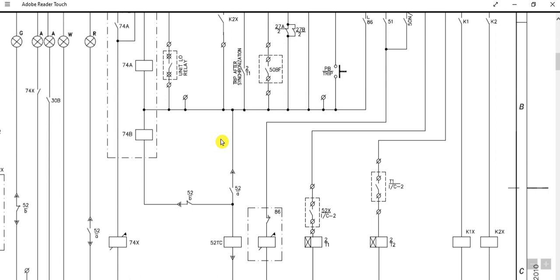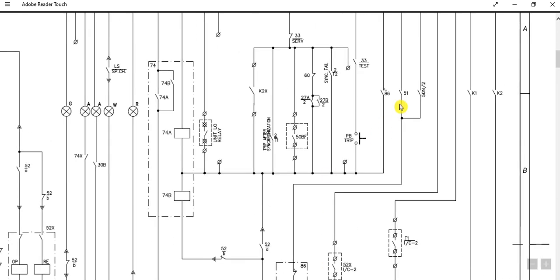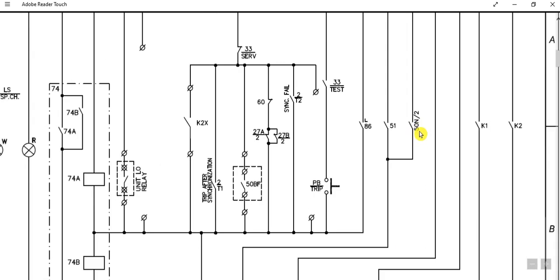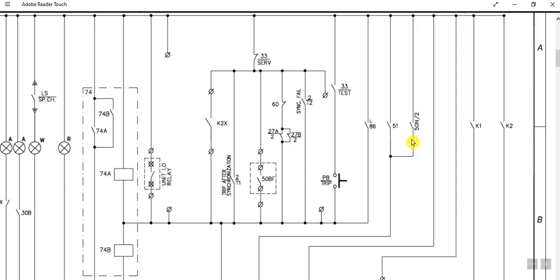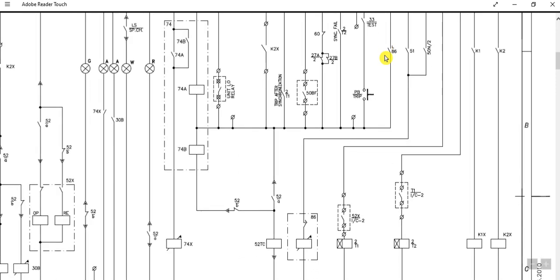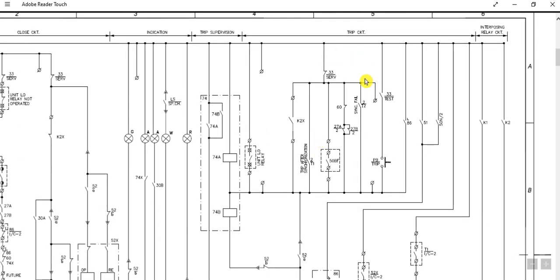There are some other options for this 86 lockout relay. It is through 51, 50N/2 — that means phase overcurrent and ground fault 50N/2 with time delay — ground fault. These are the options and part of the circuit breaker trip circuit.